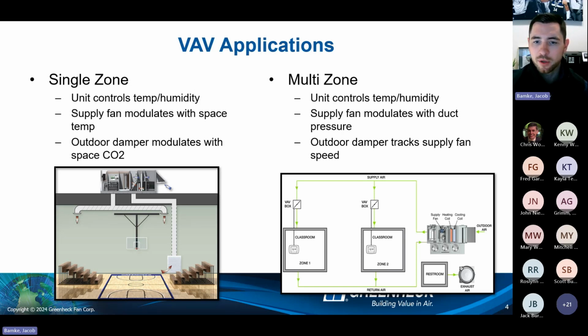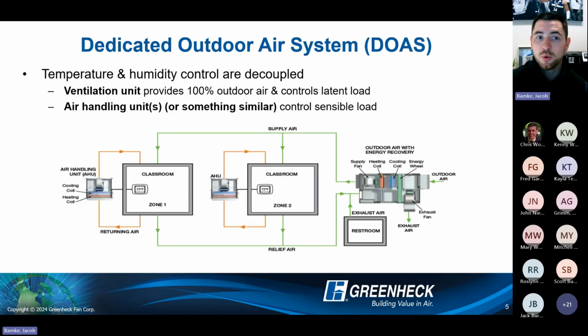So that multi-zone, we're still serving multiple spaces, but then we really transition into what ASHRAE calls a dedicated outdoor air system. I know it's a little bit different in the state of Washington, with DOAS sometimes meaning only energy recovery but still 100% outside air. In the cases that we look at in these applications, we're really trying to decouple any systems that we have. So we have that outdoor unit, whether it's this DOAS unit here with cooling or heating, or an energy recovery unit only, that is meant to provide all the ventilation.